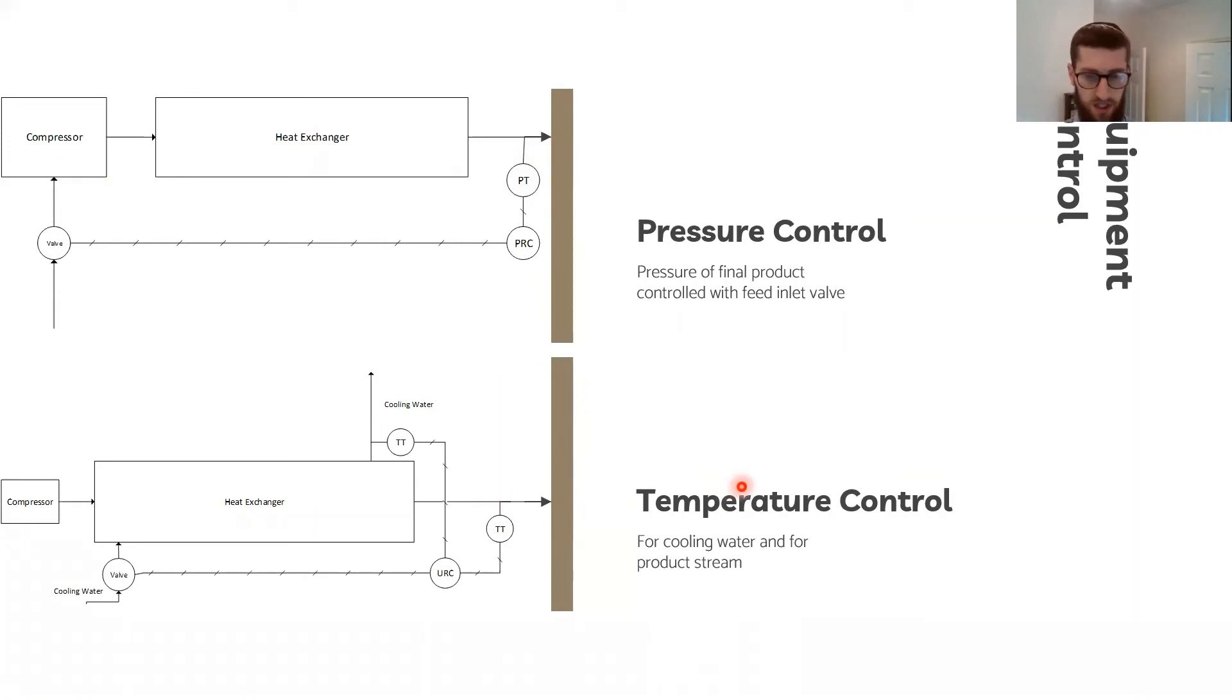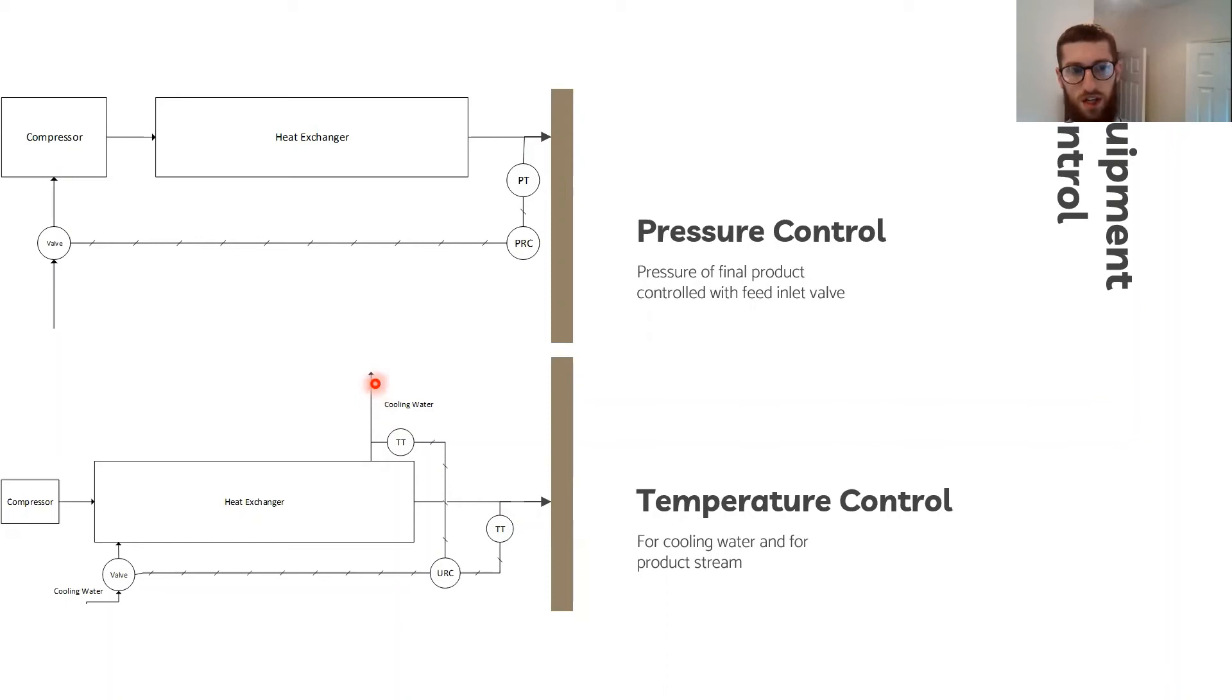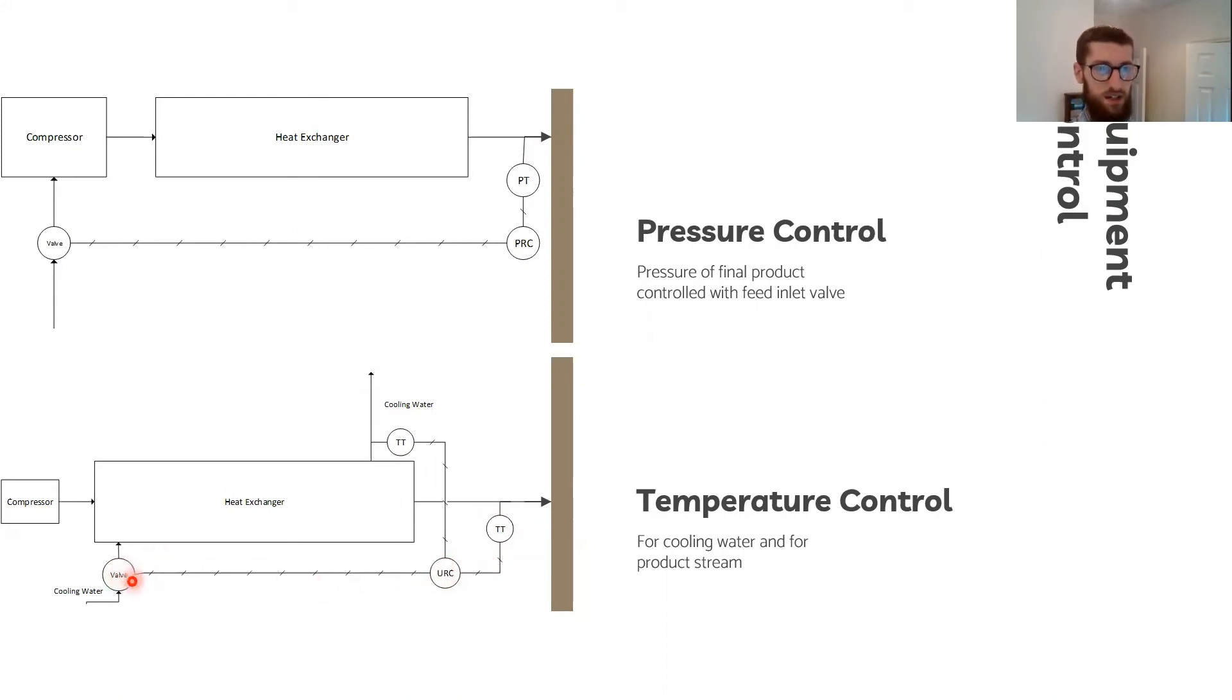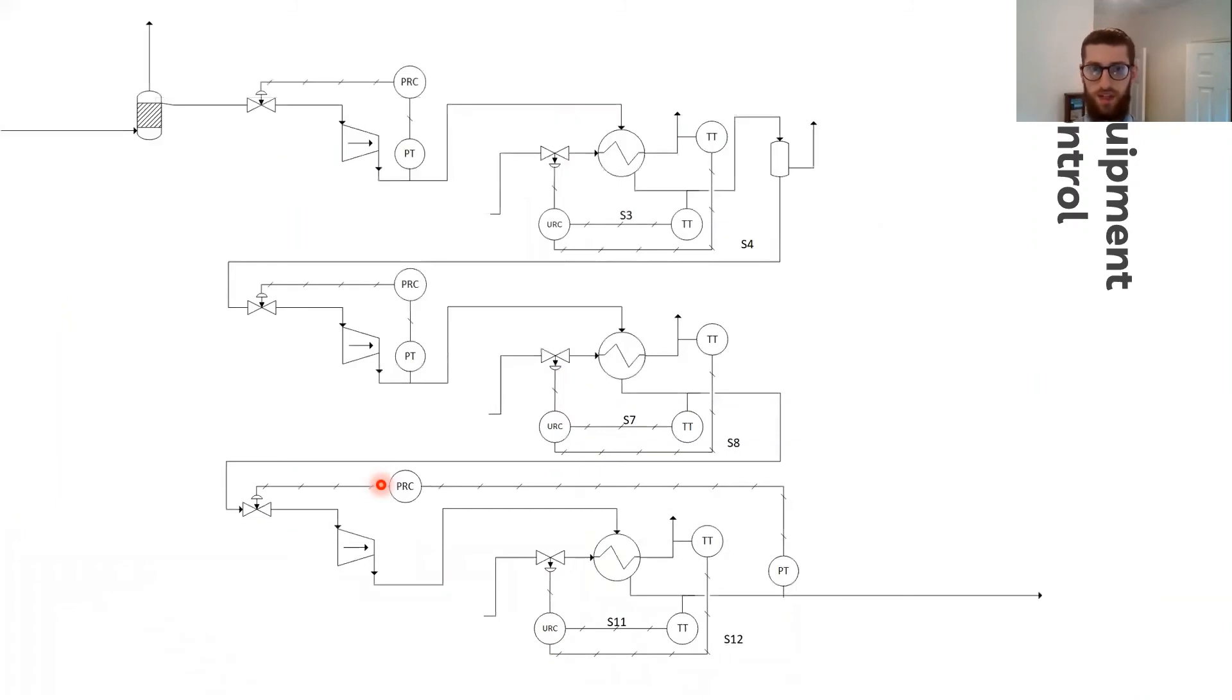For temperature, there are actually two objectives. One, to control the outlet temperature at 25 degrees centigrade, but also the temperature of the cooling water return was not allowed to exceed 40 degrees. So two thermocouples fed into a multivariable controller, and the design uses that to control the inlet feed of cooling water to the heat exchanger. This is just the P&ID of the whole compressor train.